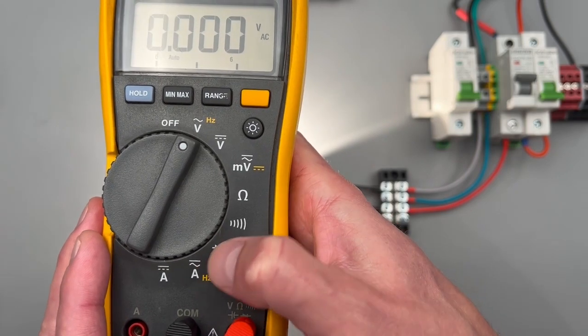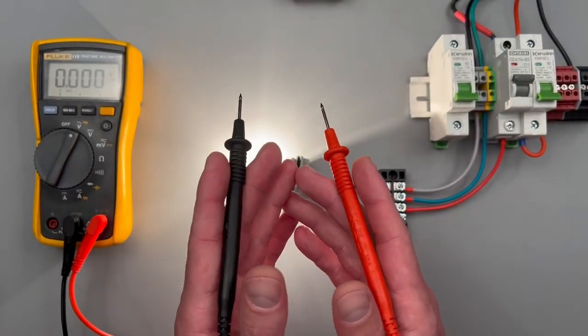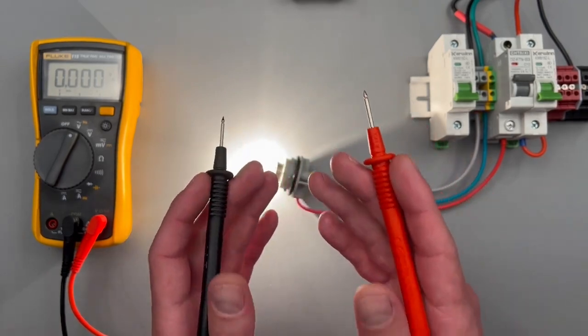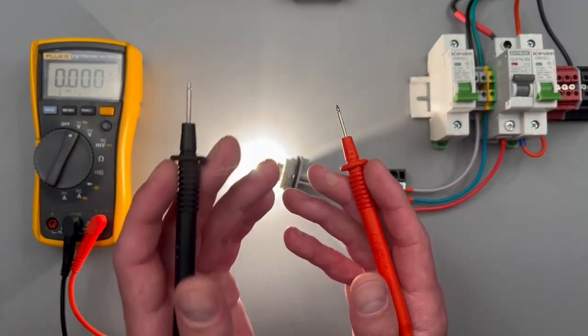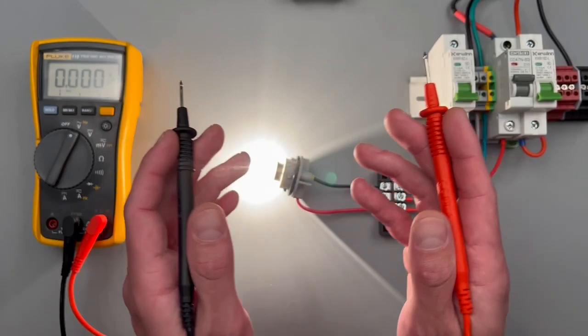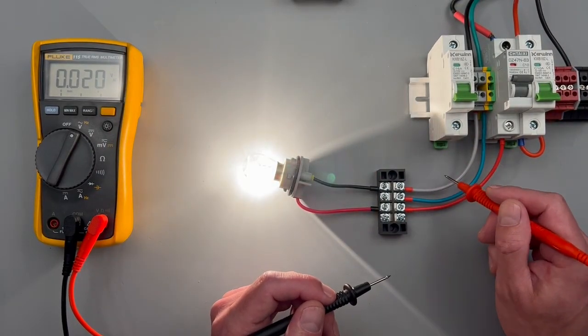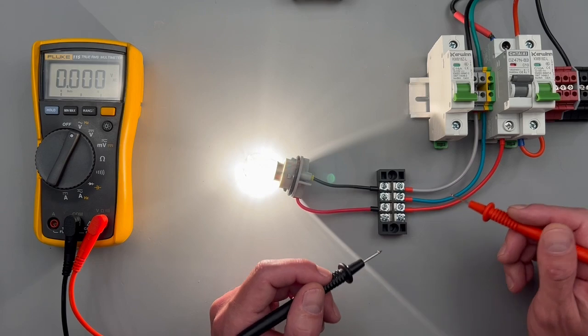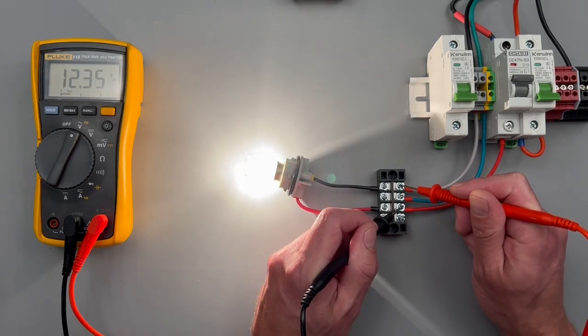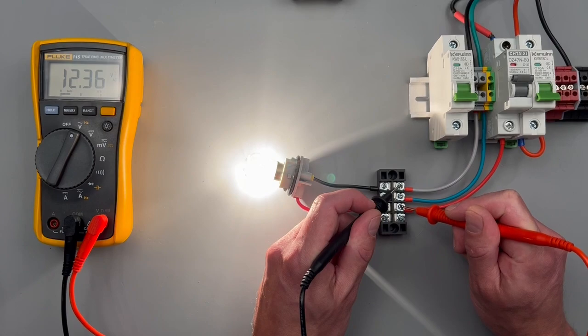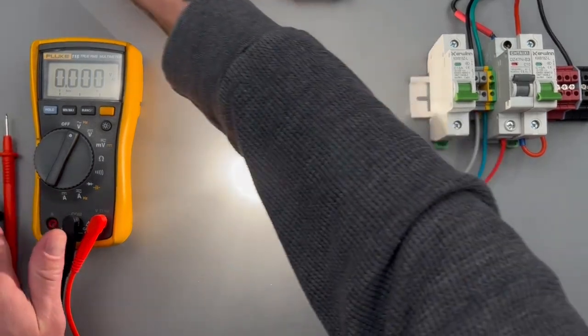With making an alternating current voltage measurement, polarity is not going to matter. What do I mean by that? I mean your black and your red lead can be in either way. This gray wire here is my neutral, this red wire here is my hot. I can make my voltage measurement in either direction and I'll still get the same voltage measurement.